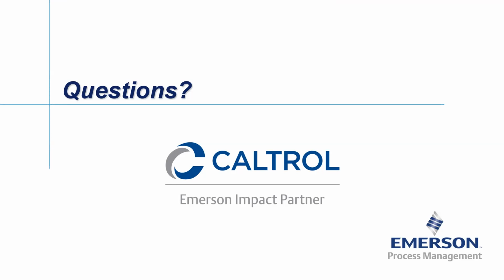But yes, the answer to your question is, if a customer suspects an imbalance, we come out and collect data on the asset before it's shut down. We can do pretty much anything we need to do, as long as we have access to the fan bearings and the motor bearings, because we'll do a combination. Sometimes a sheave or a motor can be causing the imbalance in the fan. Where everything's shaking, you may think that it's the fan that's out of balance, but it's actually something else, which is a good percentage of the time. But to answer your question, yes, we come out and analyze all of that without shutting the unit down.